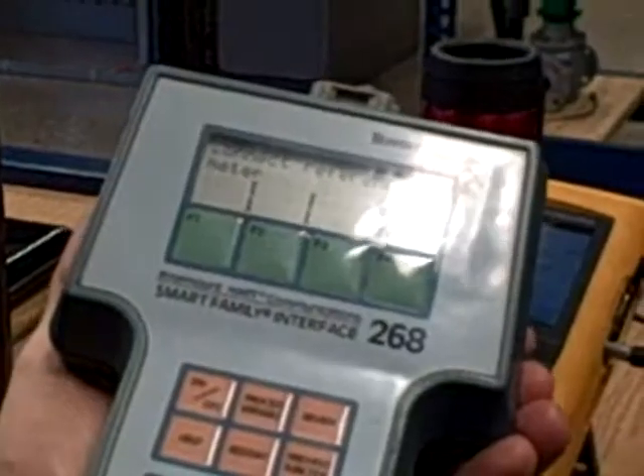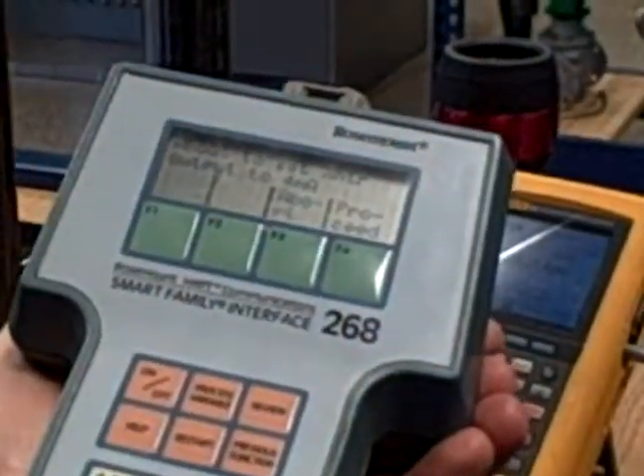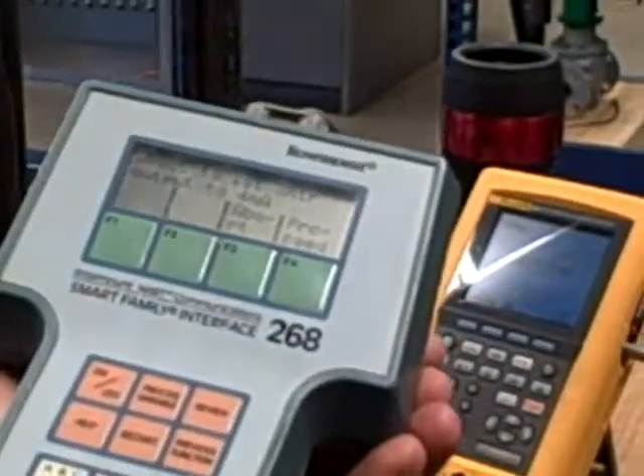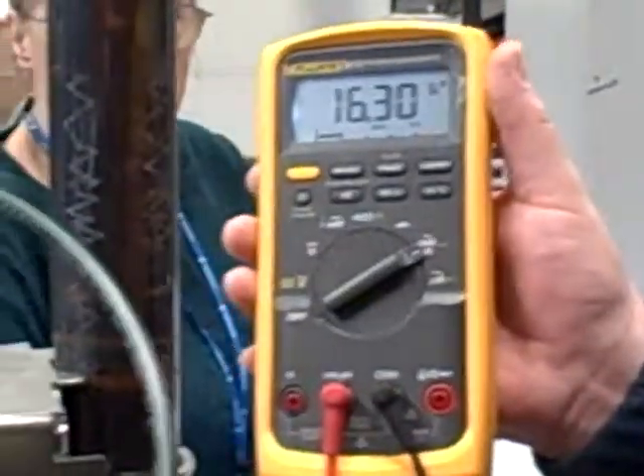Connect the reference meter. Jim's already done that. Now we proceed. About to set transmitter output to 4 milliamps. When I hit the proceed button, it will force the output to 4 milliamps regardless of the pressure coming in. It's just going to lock that output into what the microprocessor thinks is 4 milliamps. Hit the proceed button.